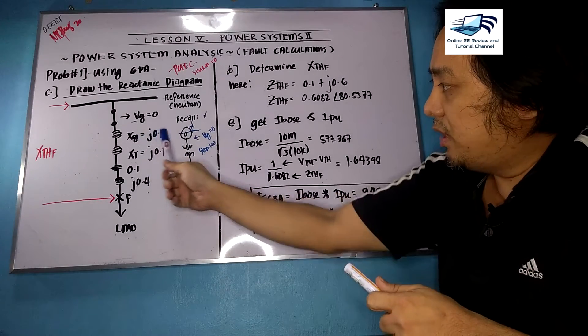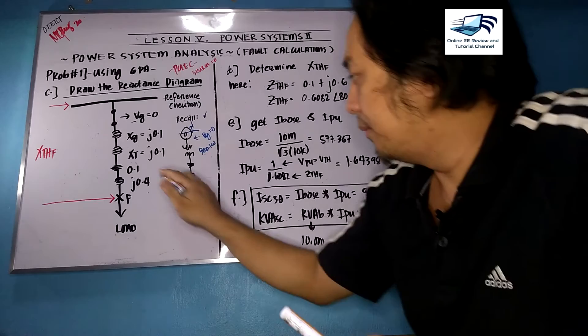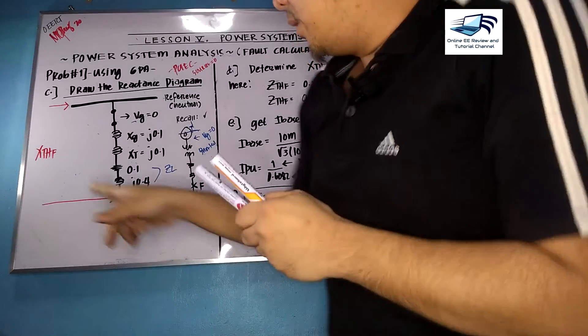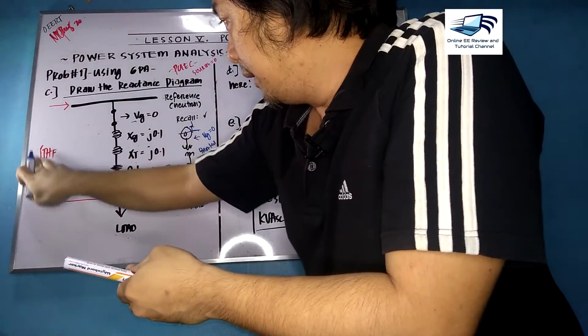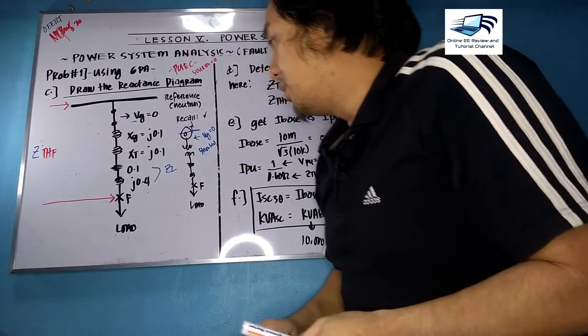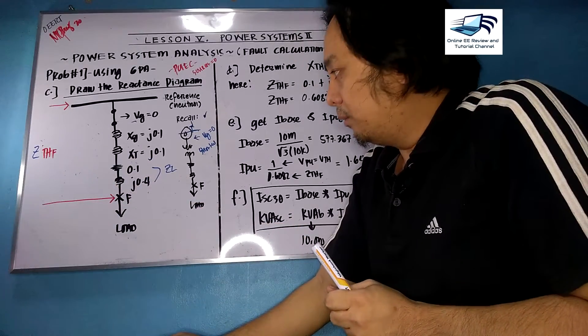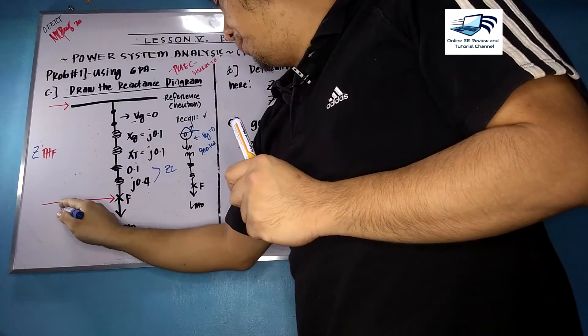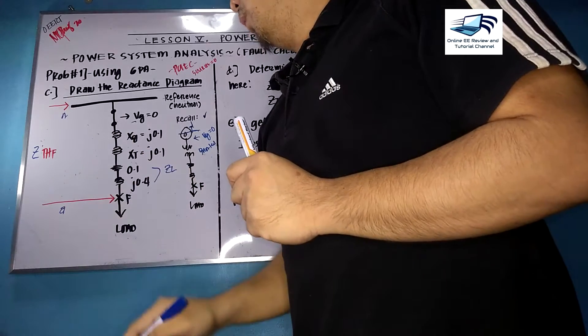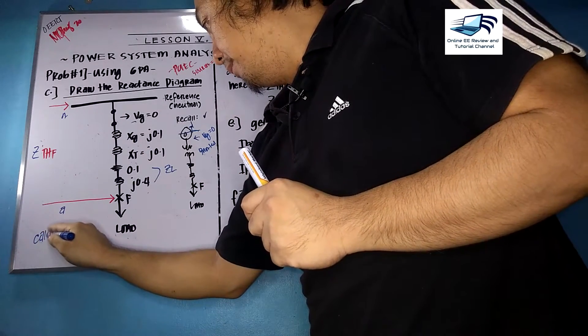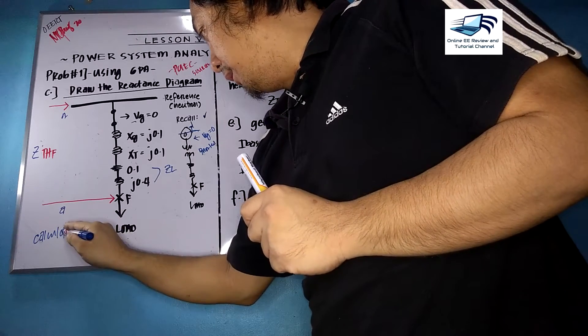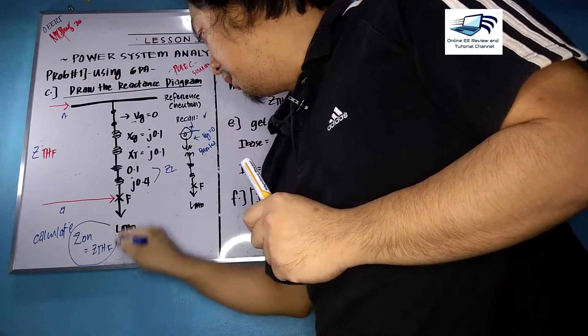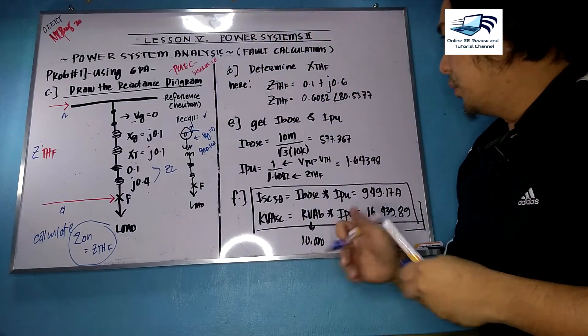Using per-unit values, we have XG = j0.1, XT = j0.1, and the transmission line impedance of 0.1 + j0.4. The fault point occurs at the load end. Since there is a resistive component of 0.1 from the transmission line, this is actually an impedance diagram. The reference is the neutral node. We label the fault point as A and the neutral as N, so we need to calculate ZAN, which equals the Thevenin impedance up to the fault point.